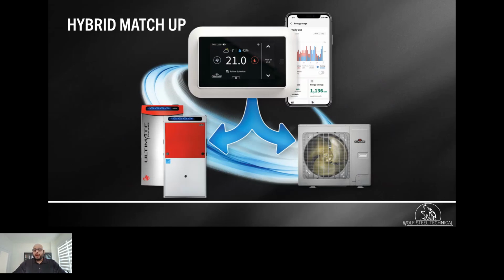In an old home, the calculations may say that a 60,000 BTU furnace and a 3-ton heat pump are recommended, but the ductwork can only handle a 40,000 BTU furnace and a 2-ton heat pump. A conversation with the homeowner must be had, explaining that either they go with smaller equipment or some renovations need to be done in order to increase the ductwork.